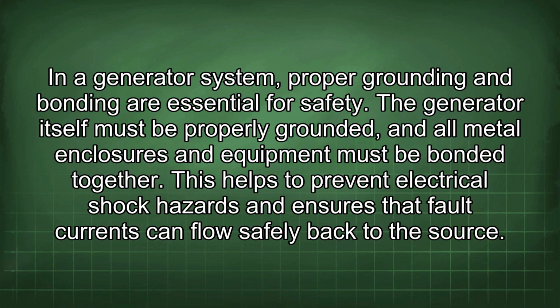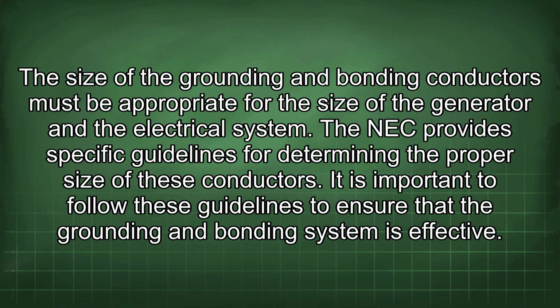The generator itself must be properly grounded and all metal enclosures and equipment must be bonded together. This helps to prevent electrical shock hazards and ensures that fault currents can flow safely back to the source. The size of the grounding and bonding conductors must be appropriate for the size of the generator and the electrical system. The NEC provides specific guidelines for determining the proper size of these conductors. It is important to follow these guidelines to ensure that the grounding and bonding system is effective.